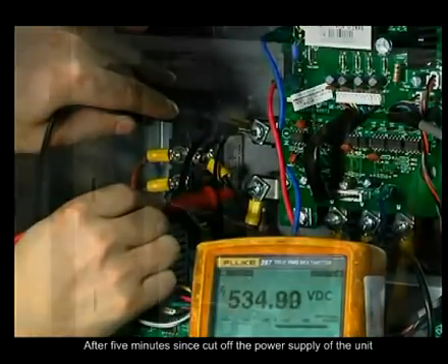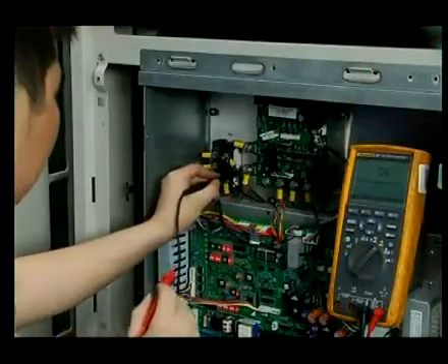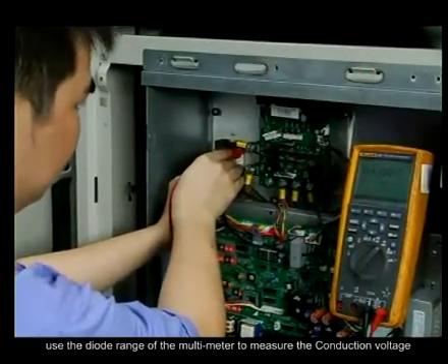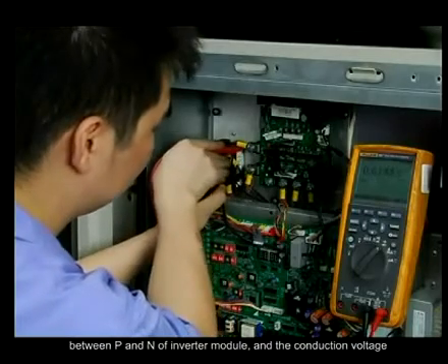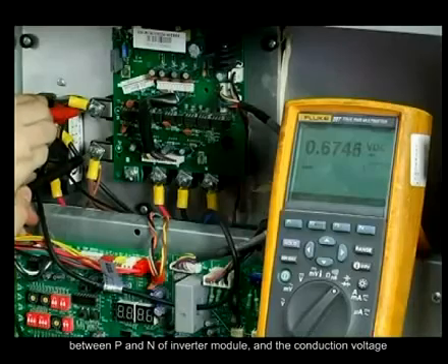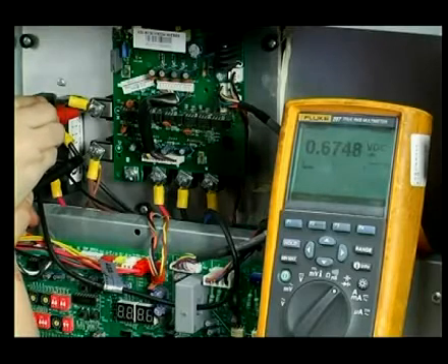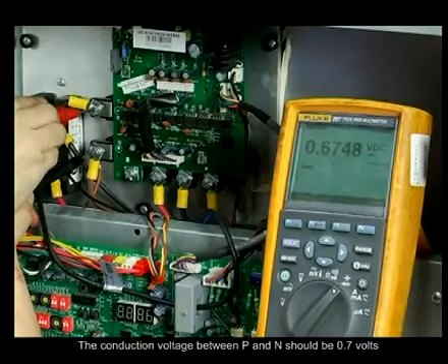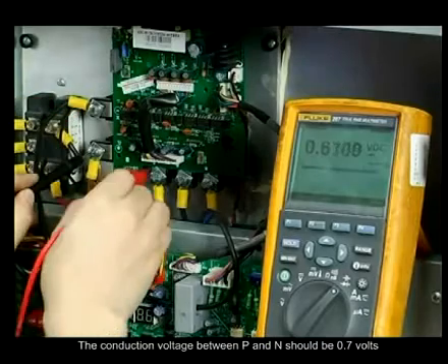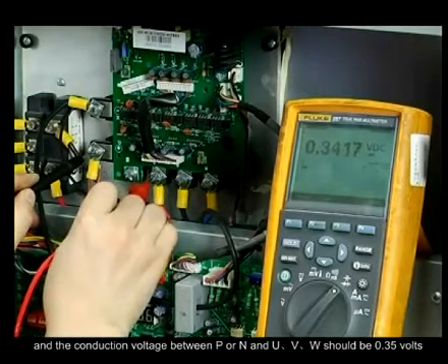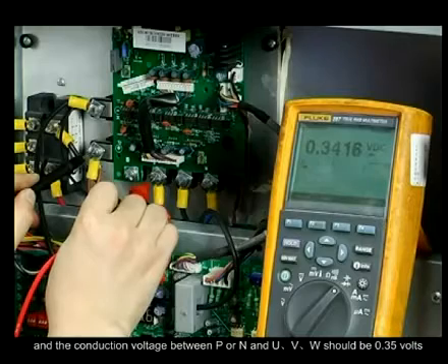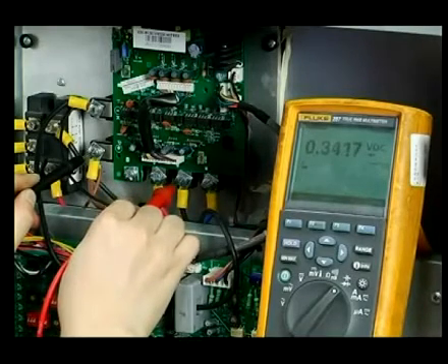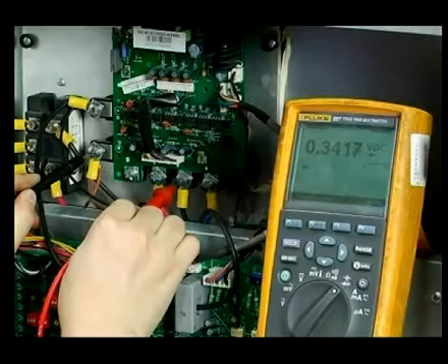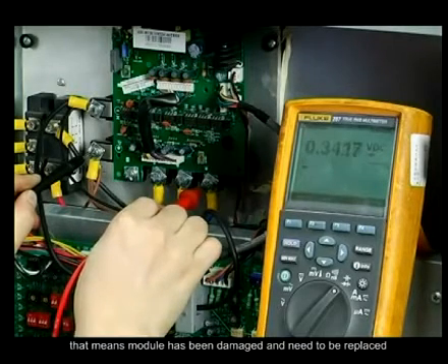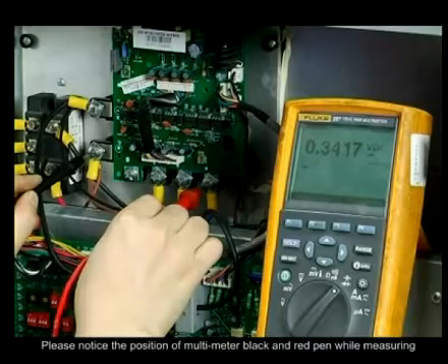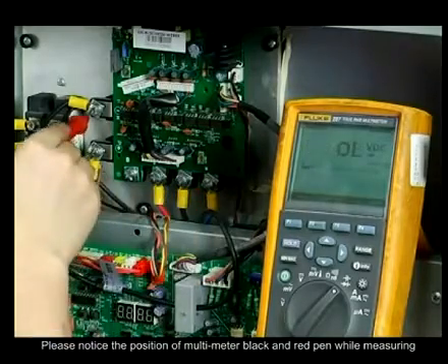After 5 minutes since cutting off the power supply of the unit, use the diode range of the multimeter to measure the conduction voltage between P and N of the inverter module, and the conduction voltage between P or N and U, V, W. The conduction voltage between P and N should be 0.7 volts, and the conduction voltage between P or N and U, V, W should be 0.35 volts. If the measured value is 0 or infinite, that means the module has been damaged and needs to be replaced. Please notice the position of the multimeter black and red pen while measuring.